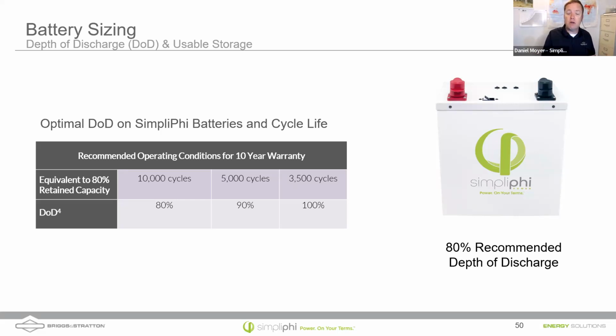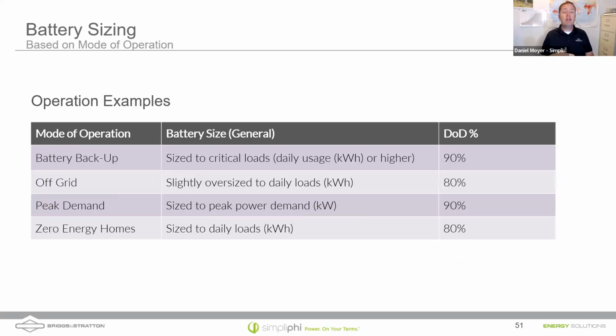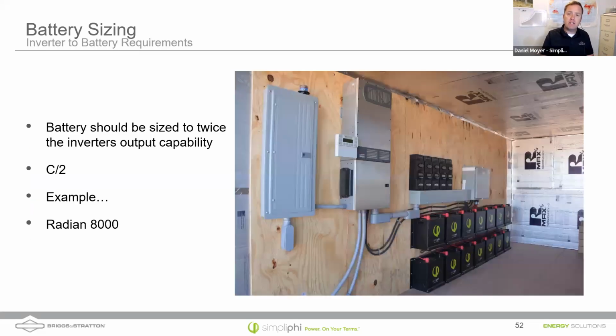Really, if you got a situation where you're not discharging the battery regularly, or maybe the battery is even just sitting there, go ahead and size that system for a 90 or 100% depth of discharge. You don't have to add a couple batteries to the system just to make sure you're only getting to that 80% depth of discharge. My example here is that 8,000 watt Radian right there.